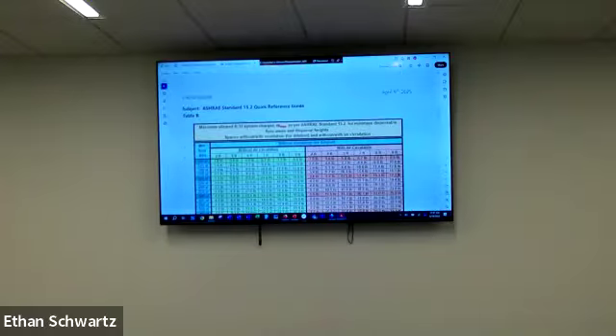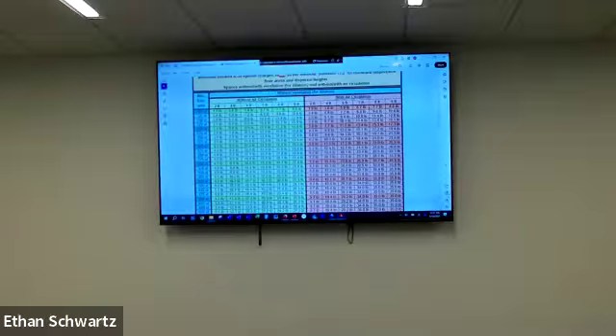Yeah, so if we look at the multi-zone right here, out of the gate we are with a 36,000 four zone, 5.5 pounds, and then the maximum refrigerant charge is 6.38 pounds. But let's take that application since that's top of mind. Now this is assuming that your four zone application is using all the refrigerant lines at their maximum lengths, and you've got 6.38 pounds. So let's go back up to our charts, and right there, it's 6.8 pounds.